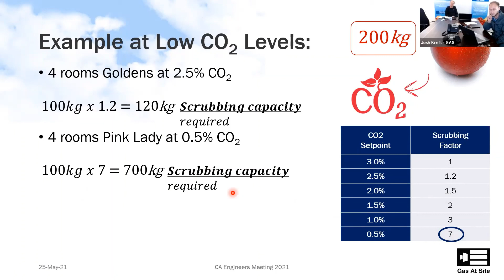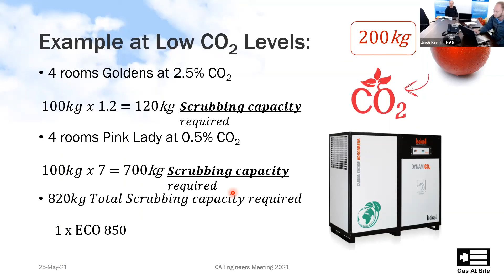And we see we need 700 kilograms scrubbing capacity just on our Pink Lady rooms. So across our 8-room complex now, we've got a total requirement of 820 kilograms scrubbing capacity, and we now need an Eco 850 scrubber. So more than double the size of the 400 scrubber in the previous example.